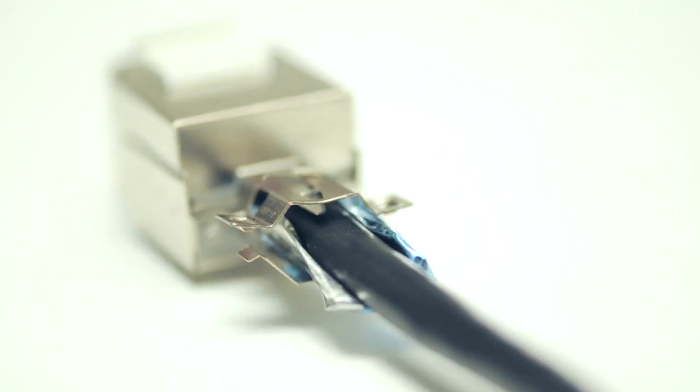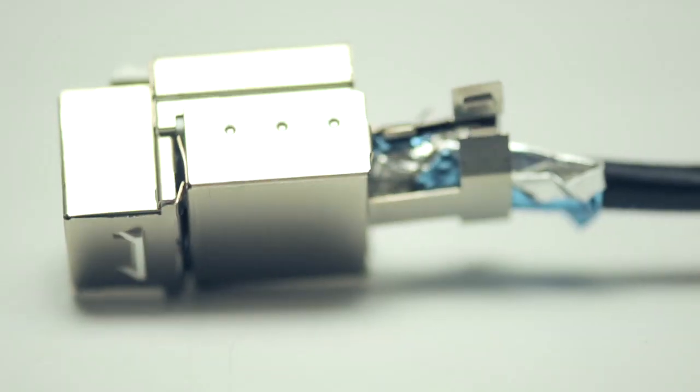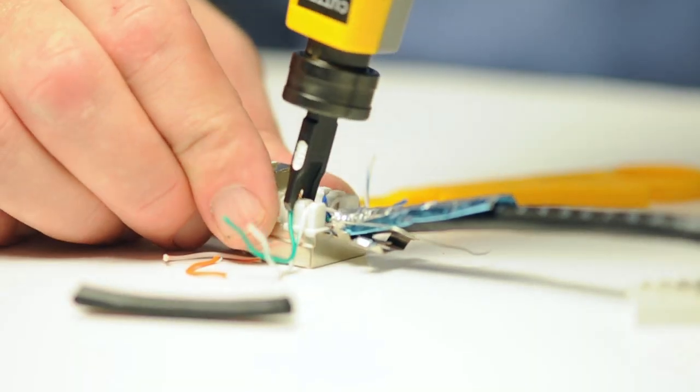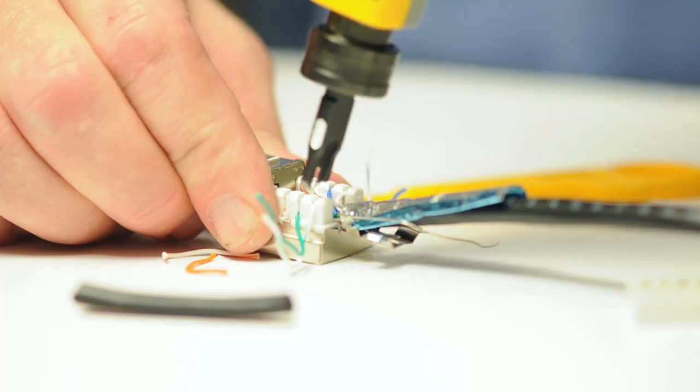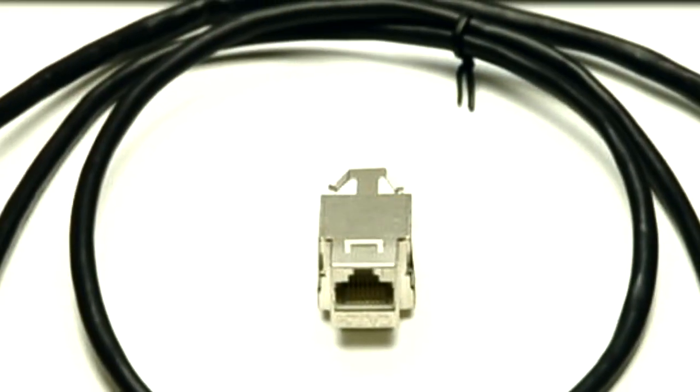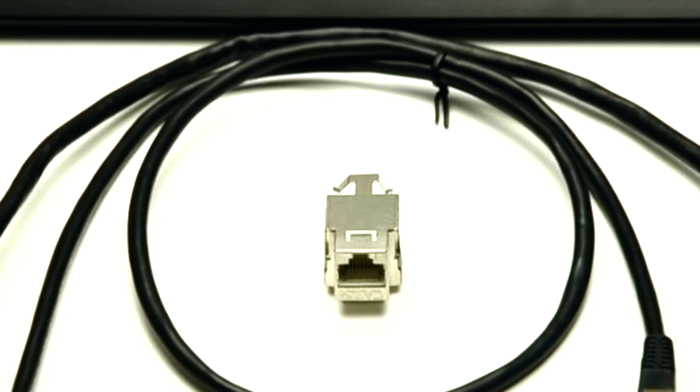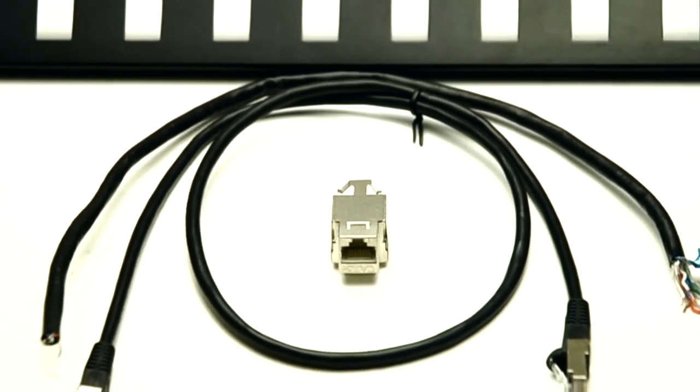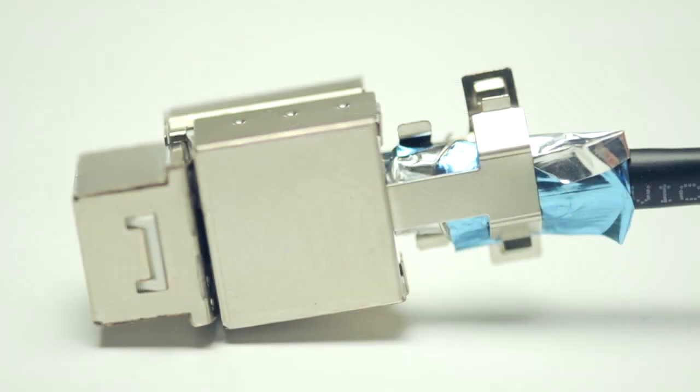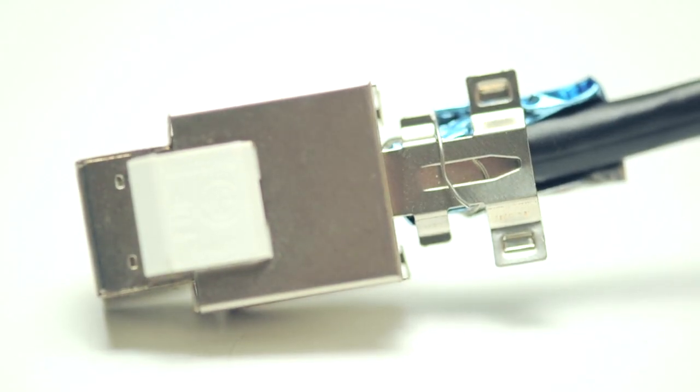Our shielded jacks have a two-piece design for easy termination. See our other video about how to properly terminate a shielded jack. The most important thing to remember is that the cable terminated to the jack, the jack itself, and the patch cable plugging into the jack must all be shielded to prevent EMI of the data signal.